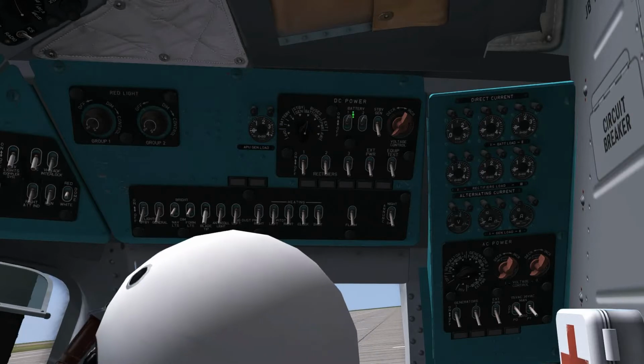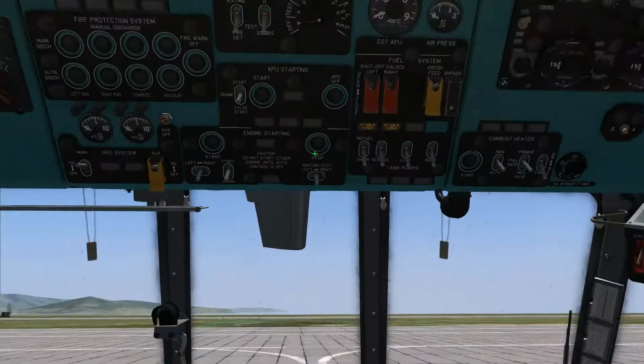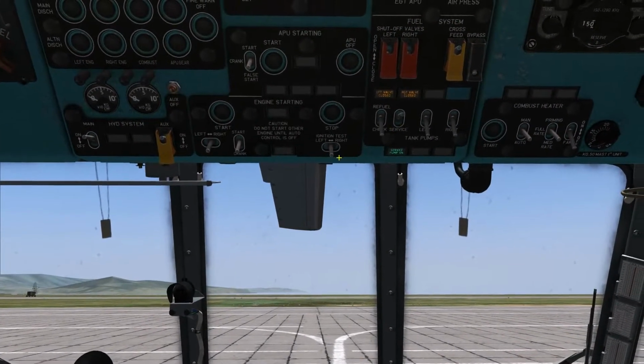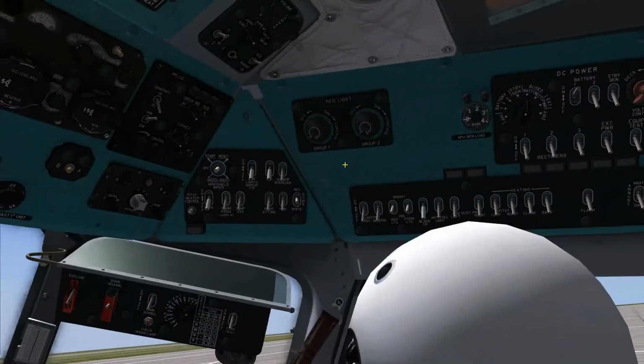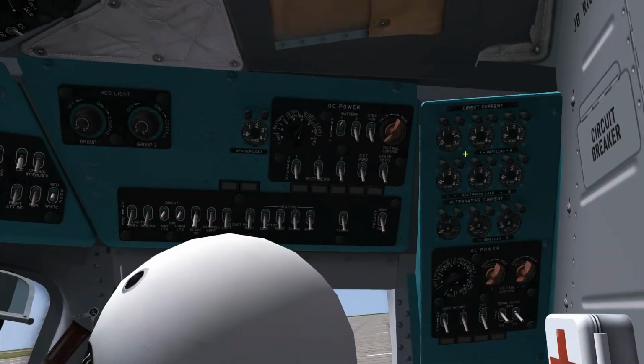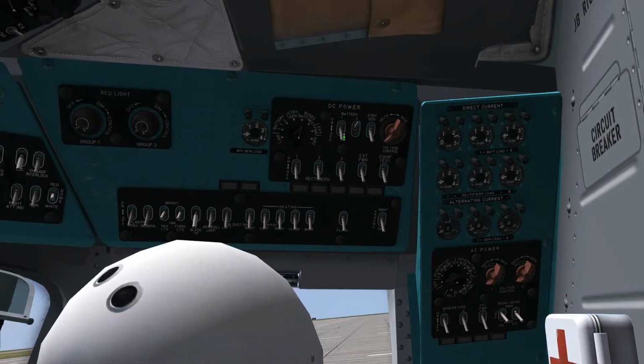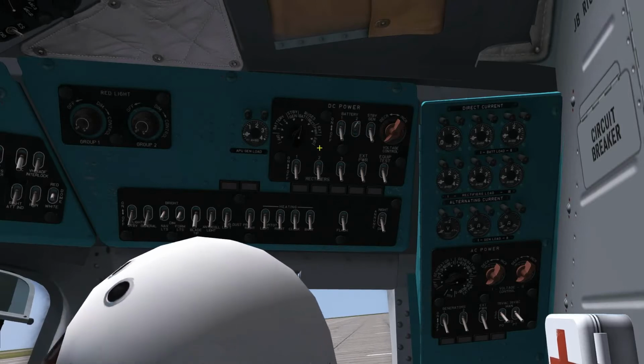Now what we're going to do is put a little bit of load on the batteries to make sure they are in good health. So we're going to turn one of them off and turn on a fuel service pump tank, which provides a load. We can see it's still above 24 volts, so that's good. You can see right there the load changes just a little bit. We do the same with battery 1, to make sure both batteries are good while under load.